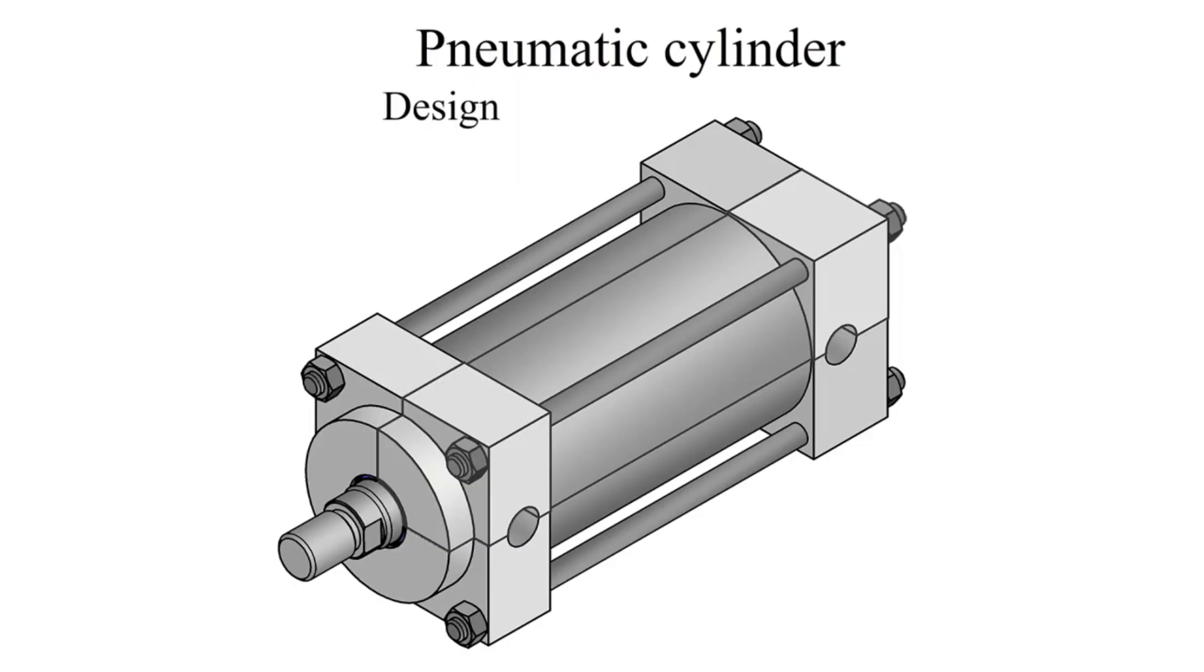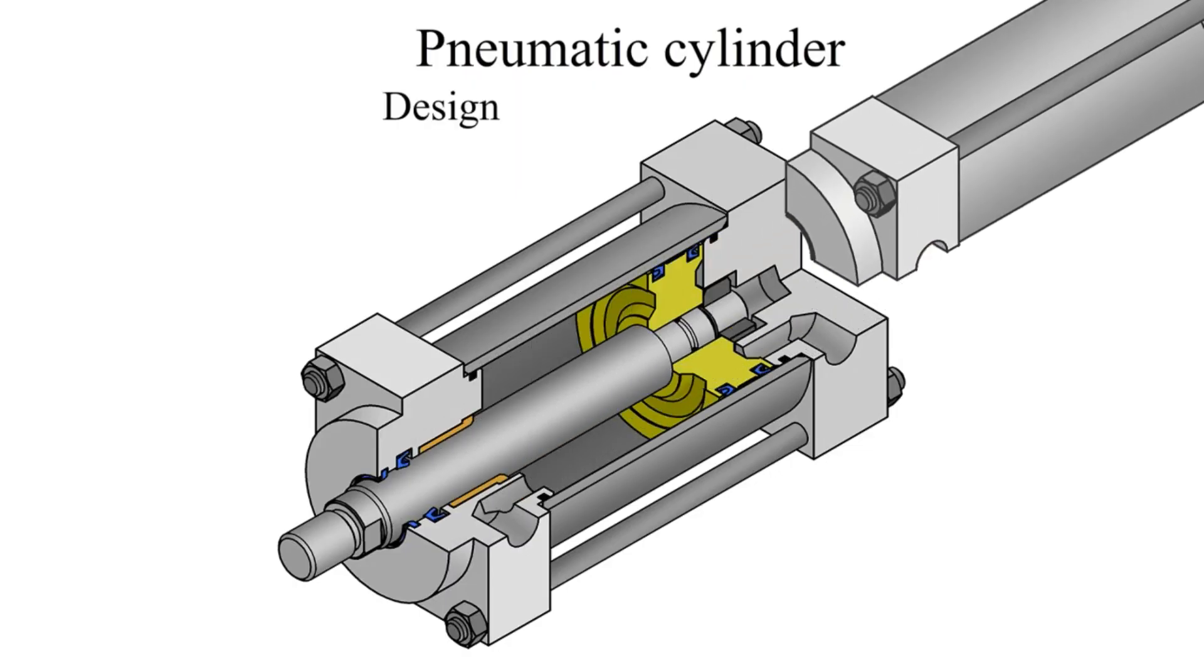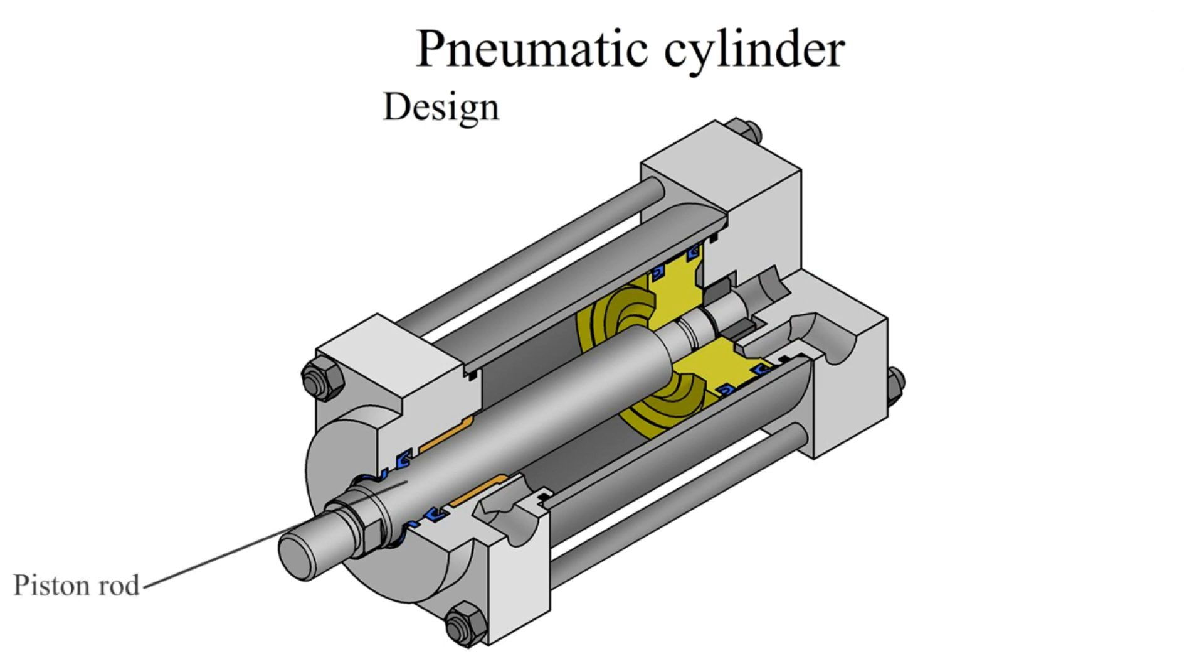Pneumatic cylinder design: The rod is a hard chrome-plated piece of cold-rolled steel which attaches to the piston. The rod is polished to provide a reliable seal and prevent leakage.